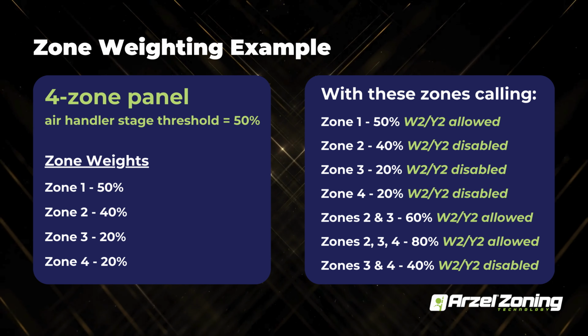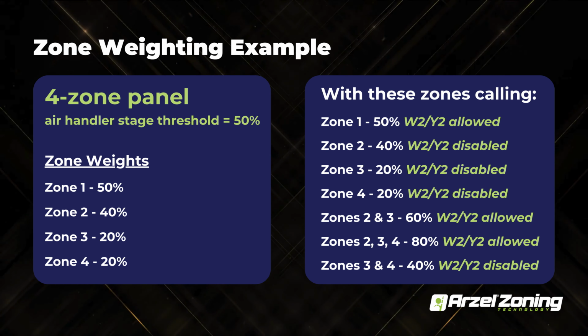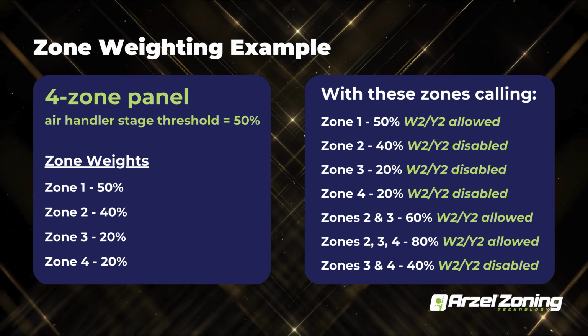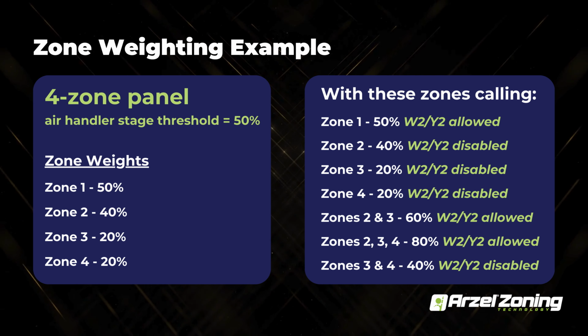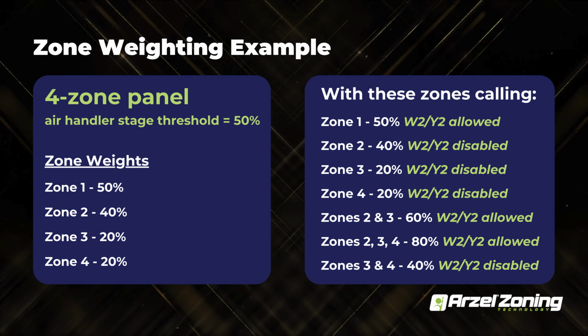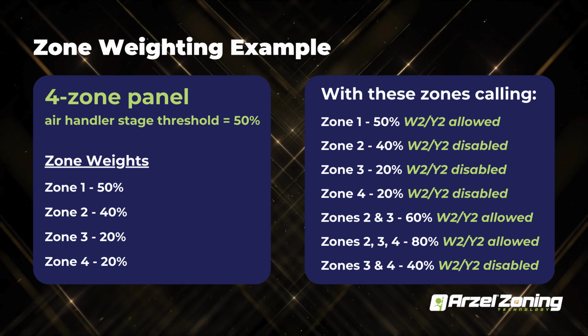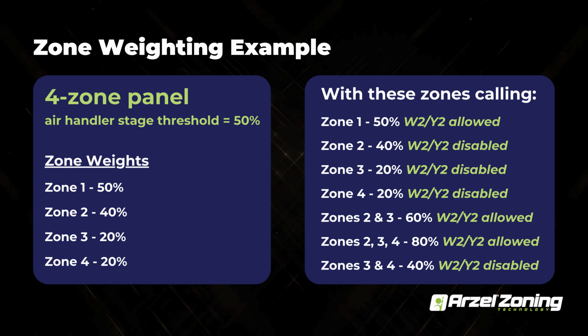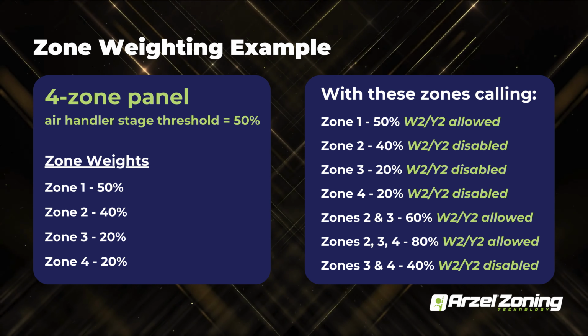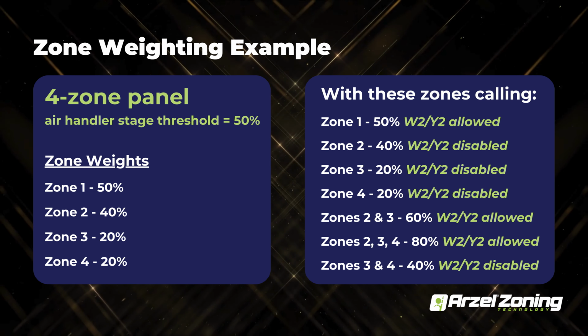But if zone 2 and zone 3 call together, it gives you that full equipment capacity. And then that last zone, it's going to be the exact same as zone 3, so it's got to call with either zone 2 or zone 1 to get full second stage output. If zone 3 and zone 4 call together, you still will not get that second stage.